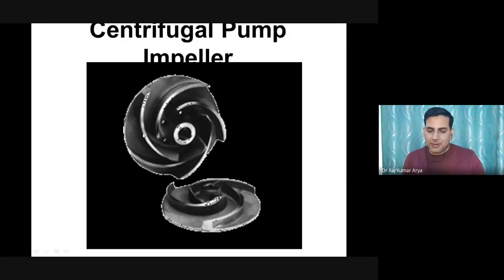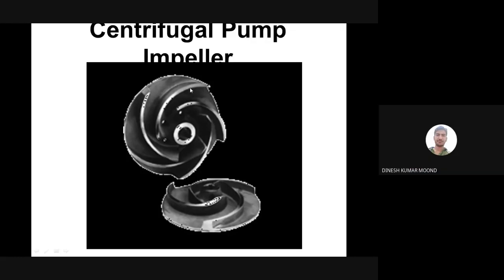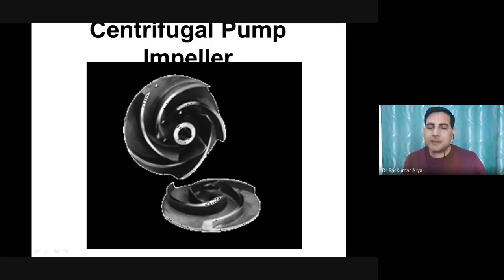Now this is the impeller we were talking about. You see here, these are some eroded marks, right? Can you see that? This is not the smooth one. Yes, sir. So this is being eroded over a period of time.